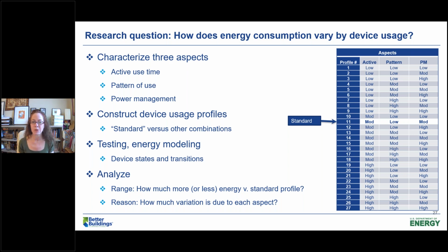So what else do we have to do? We have to do a lot of testing of those individual devices. So we see how those devices behave over time. Do they have a startup period? Do they have a warm up or a cool down? How do they act if you leave them alone? And what's the power consumption at each of those device states and each of those transitions? And then we put all of that information into this energy modeling tool that we created specifically for this, called PL-SIM, Plug Load Simulator.